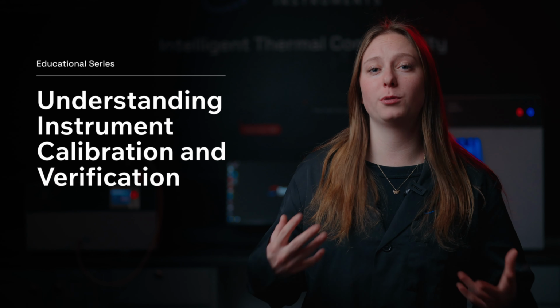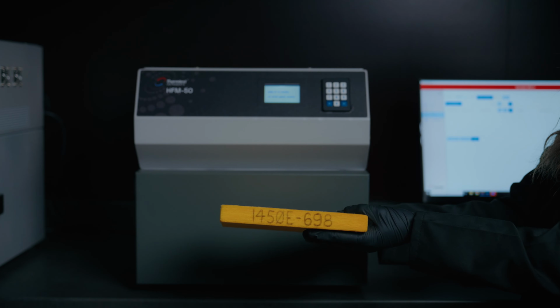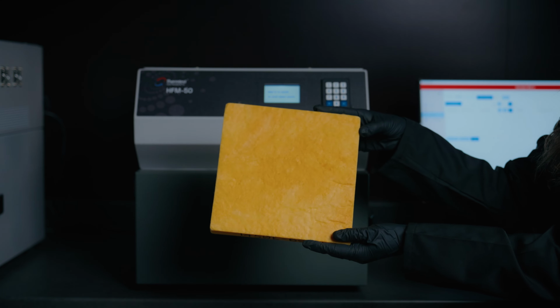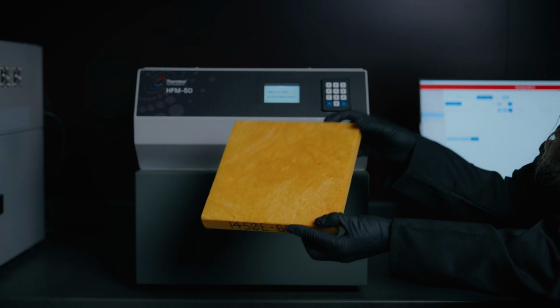That's why proper calibration and regular verification are so important. Together, they protect data integrity and ensure confidence in every measurement you make. Instrument calibration is the process of adjusting a measurement system so its output aligns with a known reference. For example, in our HFM series, a commonly used reference material is NIST 1450E, a certified reference material from the National Institute of Standards and Technology, selected for its stability and traceability.